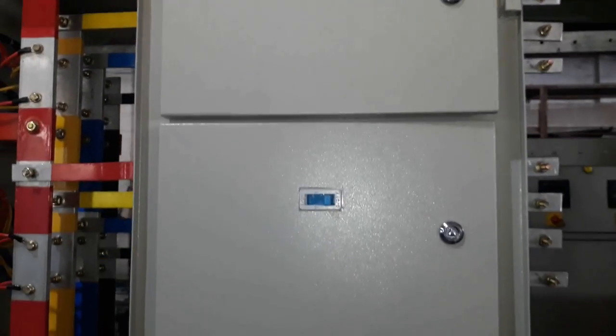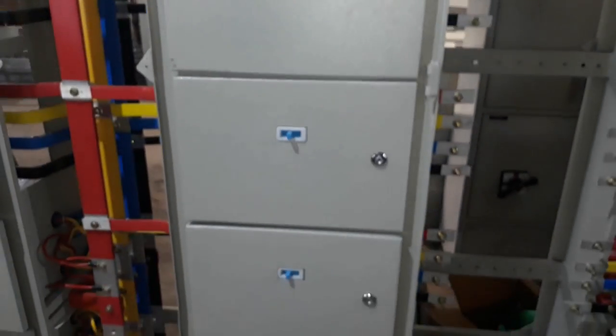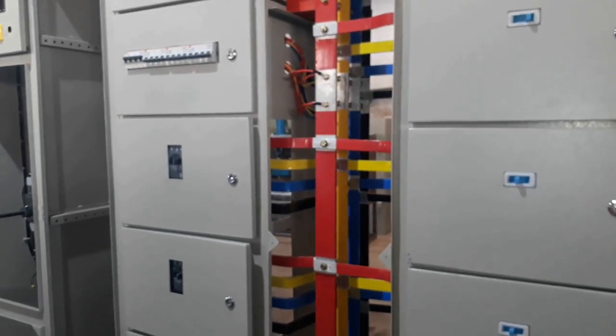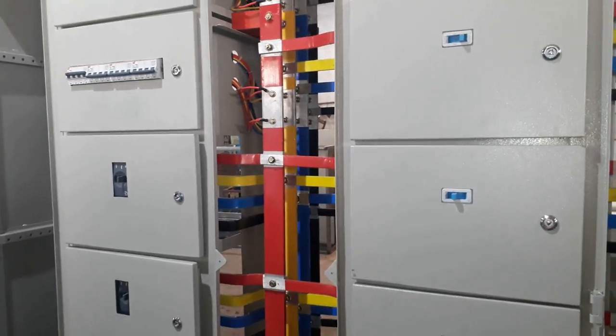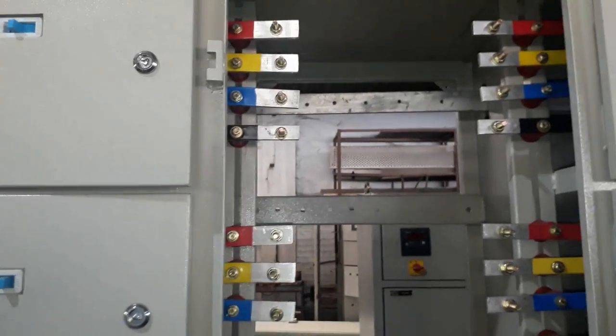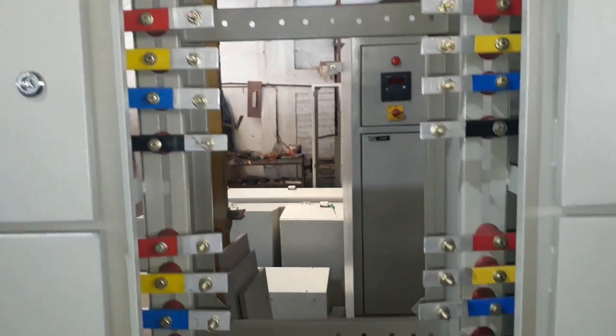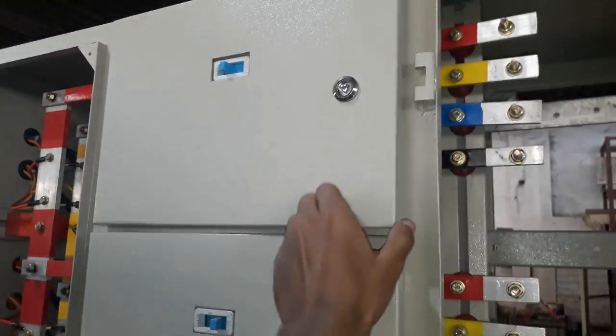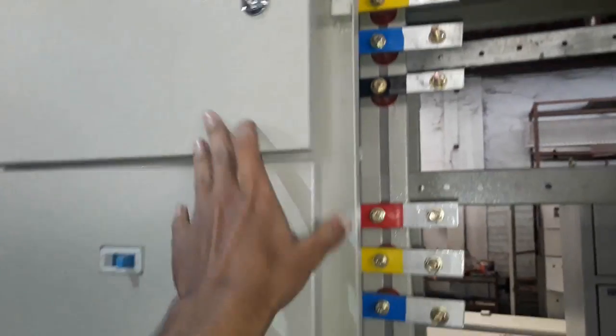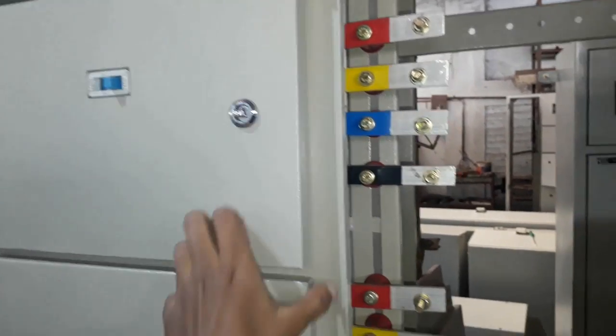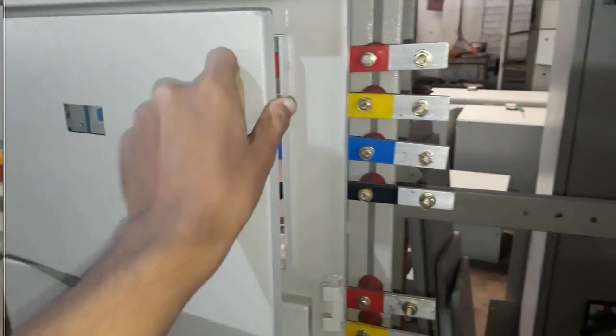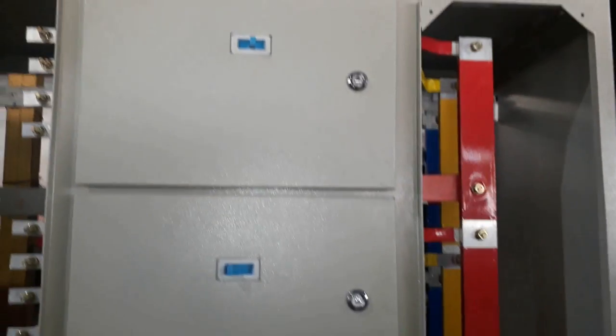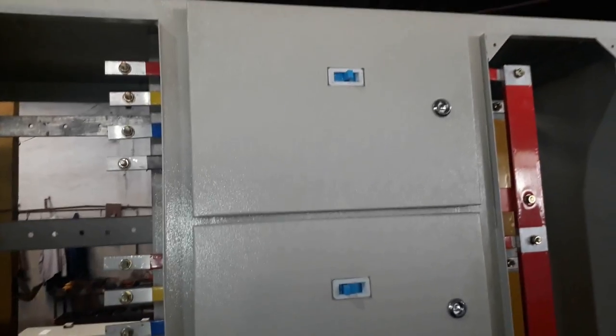From this bus bar, the power is also transferred to the circuit breakers located at the right side. Here you can see there are 3-pole circuit breakers located at the right side of this bus bar chamber. This one is an output chamber, or else we can call it a cable chamber. This one is a 3-pole circuit breaker, and the neutral is separately connected. There is also a bus bar chamber at the extreme right of the panel. These are also 3-pole circuit breakers, and neutral is connected directly.